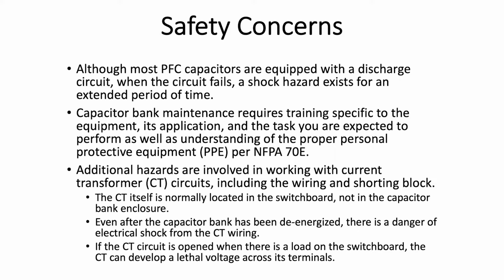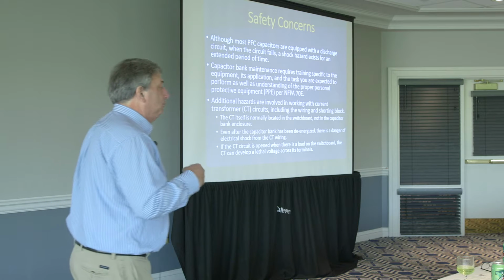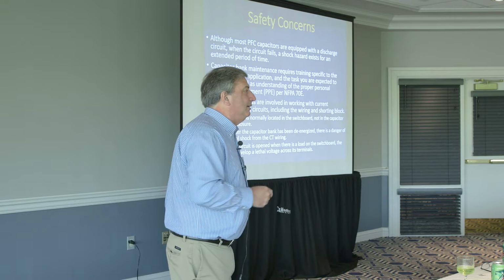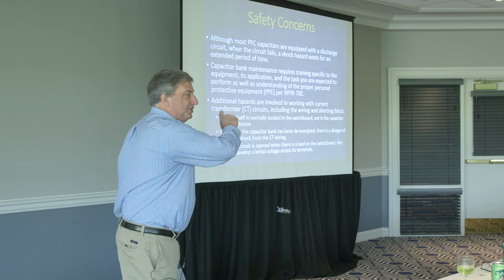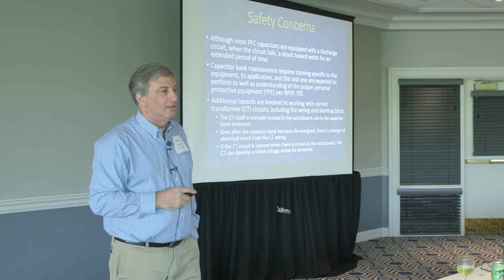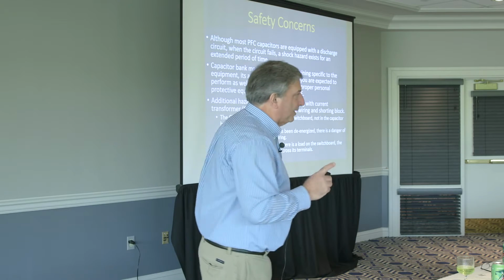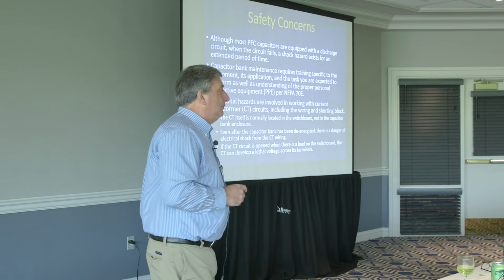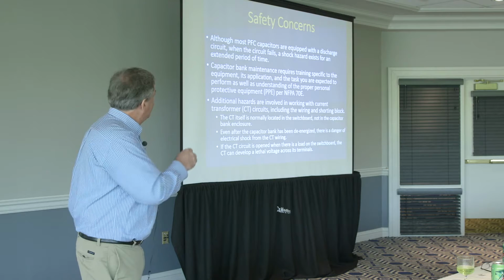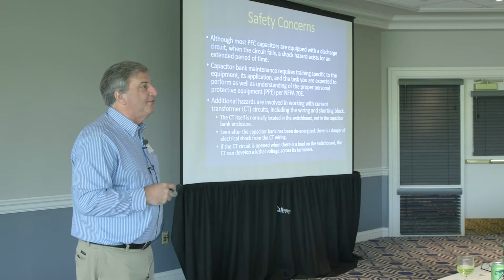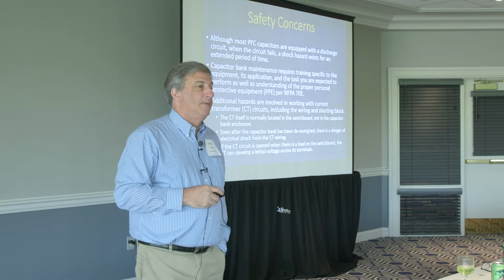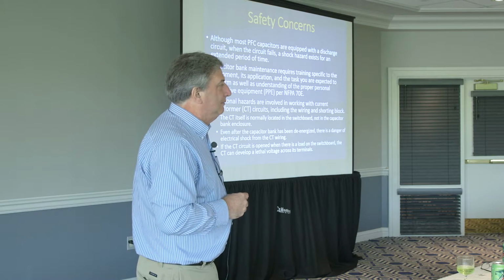Safety concerns. Most PFC capacitors are equipped with discharge circuits. When that circuit fails, a shock hazard exists for an extended period of time. So when I get involved in power factor safety issues where somebody got hurt, typically 8 out of 10 times the discharge circuit has failed and it was never maintained.